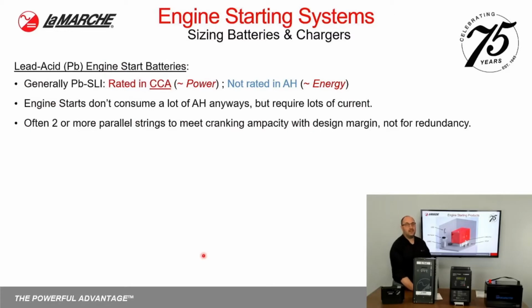So let's look at sizing a system. Lead acid batteries are generally sized and rated in cold cranking amps, not in amp hours. Cold cranking amps, you should be thinking, is synonymous with power, and amp hour rating, how much water is in the bucket, is synonymous with how much energy is available. Engine starts really don't consume a lot of amp hours. In fact, we went to test a larger 50-liter diesel engine system that was 1500 kVA. It really only consumed about 6 amp hours. I mean, we're not talking a lot of energy. What we need is power.